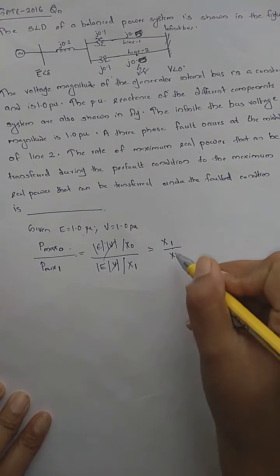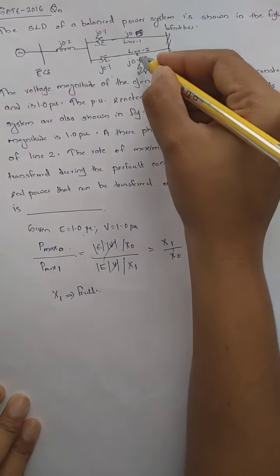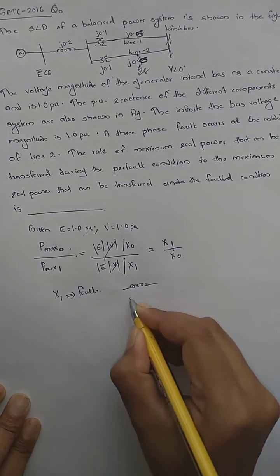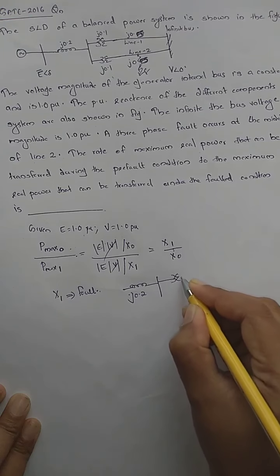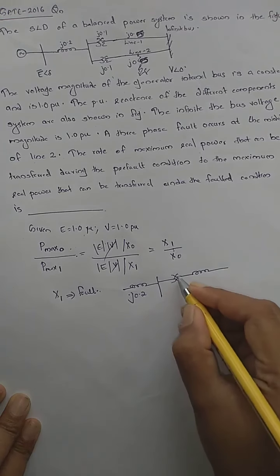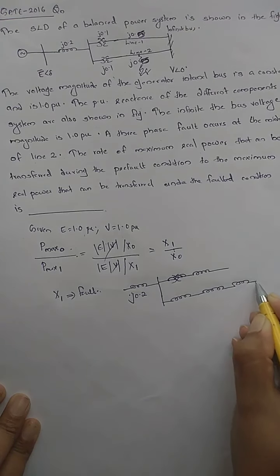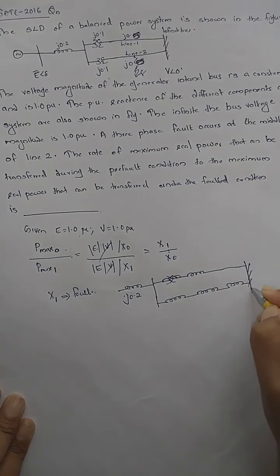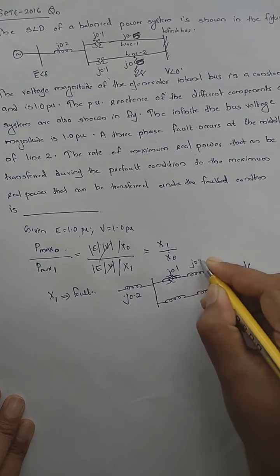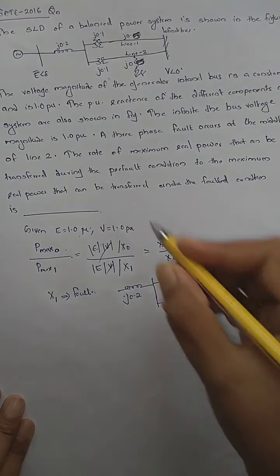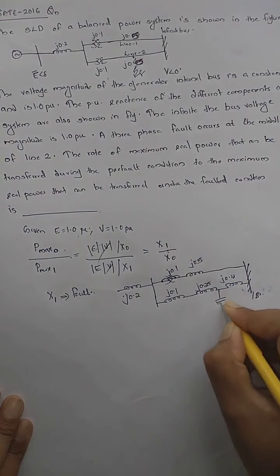X1 is the reactance under the faulted condition. Drawing the faulted circuit: J0.2 for the generator reactance, then J0.1 and J0.5 for one path, J0.1 for the transformer on the other, and the fault occurs at the midpoint of line 2, splitting it into J0.25 and J0.25. There is an earth connection at the fault point.